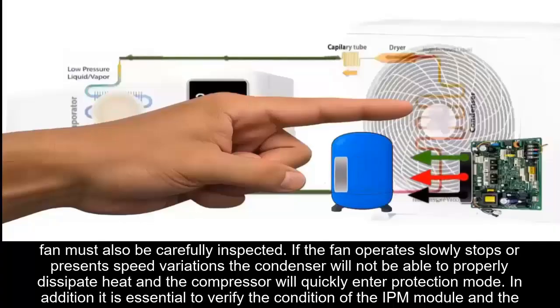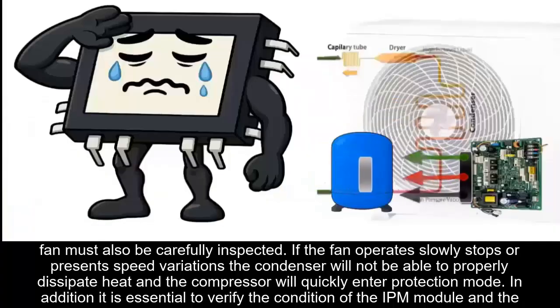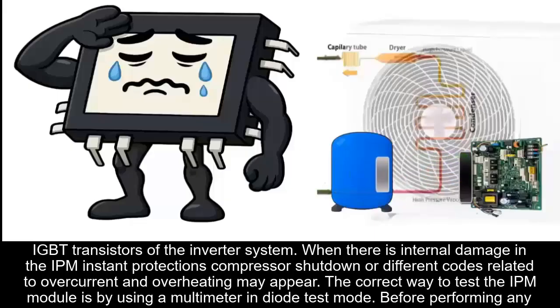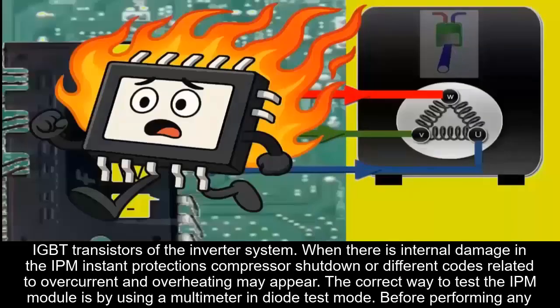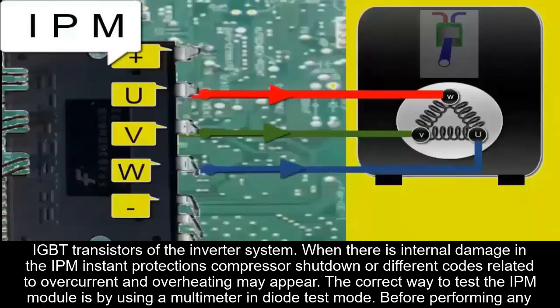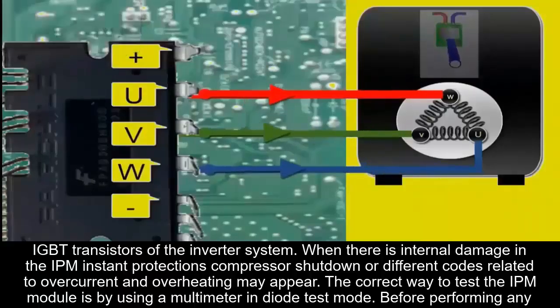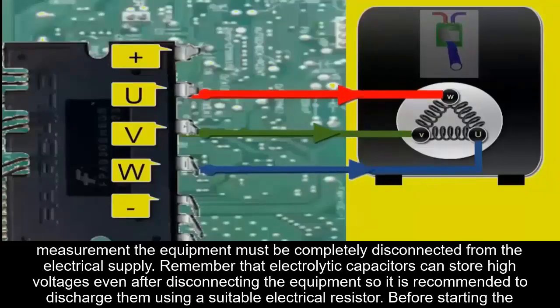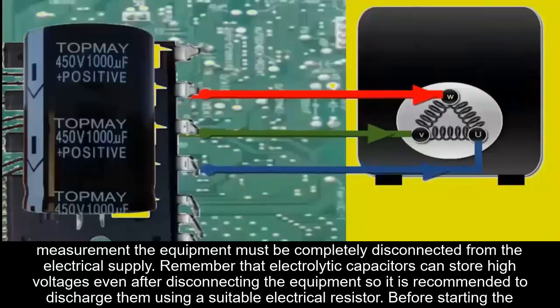In addition, it is essential to verify the condition of the IPM module and the IGBT transistors of the inverter system. When there is internal damage in the IPM module, instant protections, compressor shutdown, or different codes related to overcurrent and overheating may appear. The correct way to test the IPM module is by using a multimeter in diode test mode. Before performing any measurement, the equipment must be completely disconnected from the electrical supply. Remember that electrolytic capacitors can store high voltages even after disconnecting the equipment, so it is recommended to discharge them using a suitable electrical resistor.